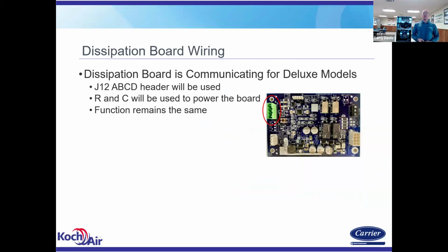If you're on a communicating system and you're using a communicating wall control, the board does communicate. You do still have to send a separate 24-volt power to the board. You don't use your C on the communicating plug. That power, the R, comes before the fuse on the furnace board. It's right off the transformer output. Okay.